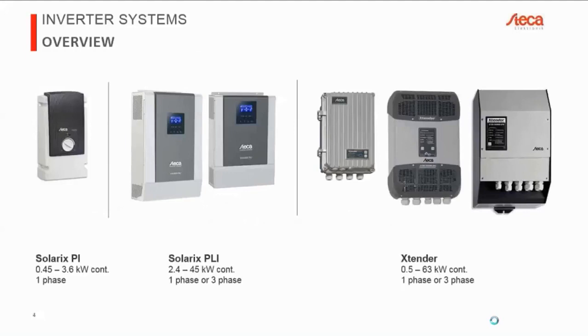Here you can see our main portfolio of inverters. On the small side, on the left, we start with the SOLARIX PI. They come in 450 watt and 900 watt units, and you can put up to 4 of them together on a single phase, so that we end up with a total system size of 450 watts to 3.6 kilowatts continuous power. All of the powers I'm giving you today are continuous power. Depending on the device, sometimes we have a higher 30-minute power rate, and for all of the devices, we have a certain overload capability, a peak capability for 5 seconds. So what I'm talking about here is the continuous power. So this is for pure single-phase loads. There's no connection at all to any grid, so this is really for a pure off-grid scenario.